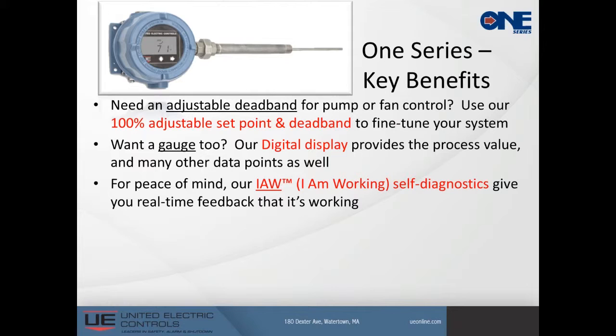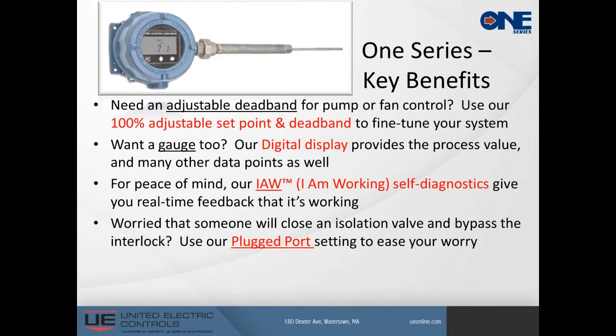In a lot of cases, there's a lot of discussion about proof testing on mechanical and electronic devices, including transmitters. And it has been determined in a lot of proven in use scenarios that the 1 Series, with its self-diagnostic capabilities, needs less proof testing than mechanical devices, and in fact some transmitters, because it tells you its health. That health can also be remotely located back to your PLC or your DCS as a human interface, an HMI. So now the operators even know the health of this device as it is out in the field. And of course, I talked a little bit about the plug port capability that this product has as well.